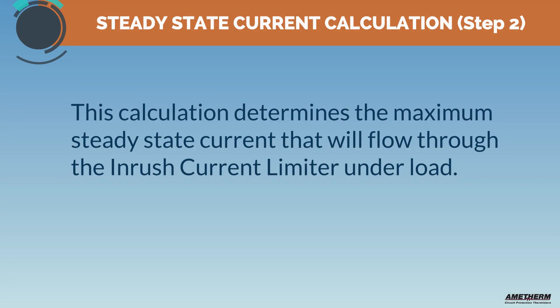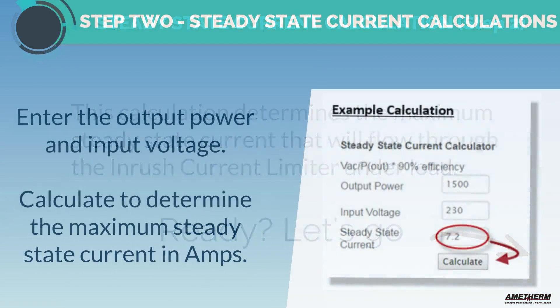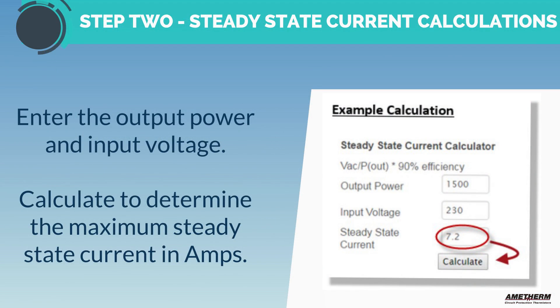Step 2: Calculating the steady state current. This calculation determines the maximum amount of steady state current that will flow through the inrush current limiter under load. Enter the output power and the input voltage, then calculate to determine the steady state current in amps. In this scenario, it is 7.2 amps.